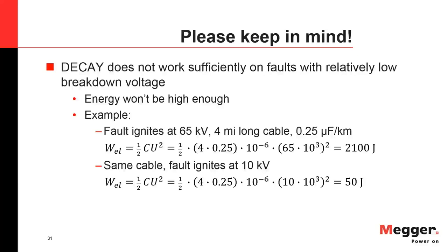Now, if you would do a fault location on the same cable and the fault is only 10 kV and you attempt to use DECAY, you only get 50 joules. That is below any audible or anything. So this is not usable because the surge energy is not high enough. So DECAY is exclusively a technique for high resistance, high voltage, high ignition voltage faults, because of that very reason, you need the energy.